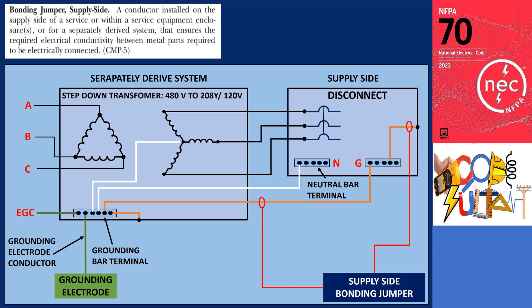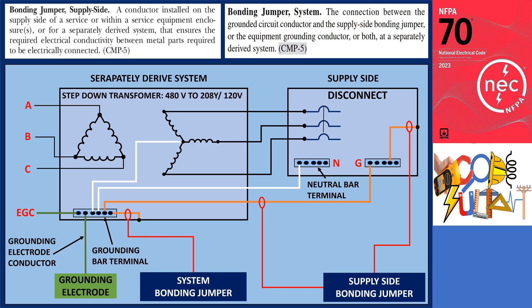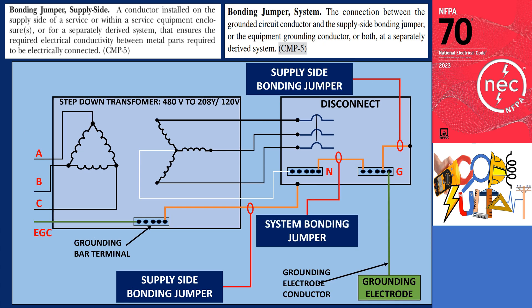A system bonding jumper is the connection between the grounded circuit conductor and the supply-side bonding jumper or the equipment grounding conductor, or both, in a separately derived system. It is used to connect the equipment grounding conductors or the supply-side bonding jumper to the grounded conductor of a separately derived system. The system bonding jumper can be located at the source or at the first system disconnecting means, as shown in another illustration. This type of bonding jumper ensures an effective path for ground-fault current to return to the source. Similar to the main bonding jumper at the service equipment, the system bonding jumper provides the necessary link between the equipment grounding conductors and the system grounded conductor to establish an effective path for ground-fault current to return to the source.